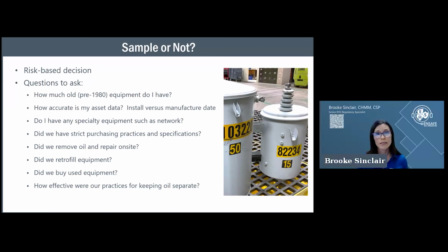I mentioned the great properties that PCBs have, and those types of network equipment, in special locations and buildings, are where you might have spent more money to get PCBs in your oil. So you definitely want to target those areas as well. Did you restrict your purchasing practices and specs, or did you just kind of get what you got? The more restrictive you were, the more likely you did not get PCBs in your system. I'd say that's more true for substation equipment than a smaller pole-top or pad-mount transformer, and that can help you make some risk-based decisions.